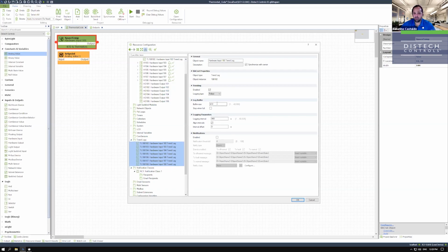But for those of you who want more, you could double that, get 14 days, you triple it, and you're still going to be well within, from this perspective, I think it's roughly around 370 points trended for a week. That's a lot of points to trend, maybe in a plant controller you're getting closer to it, but for typical applications, maybe you trend 50 points, maybe even that's saying a lot.